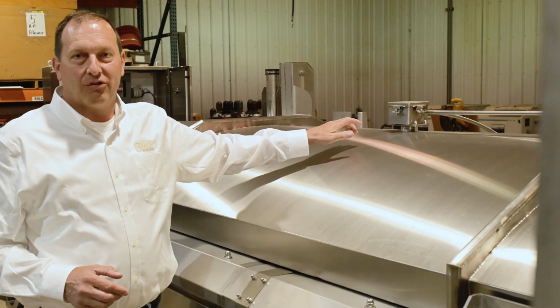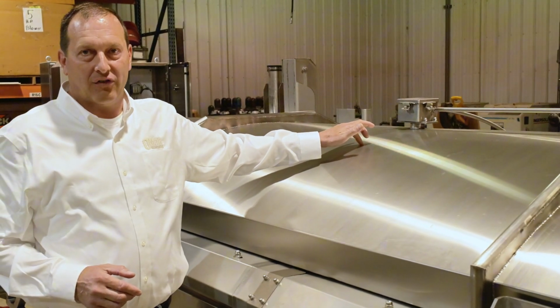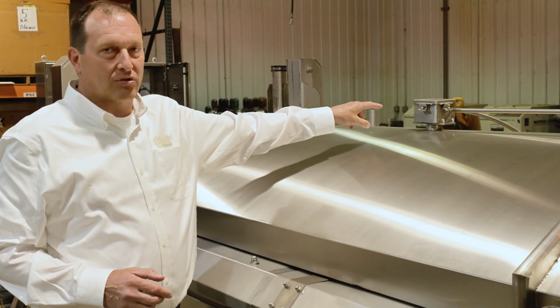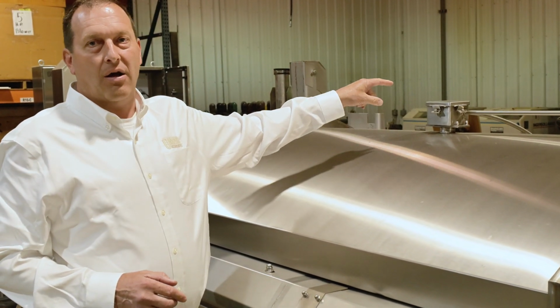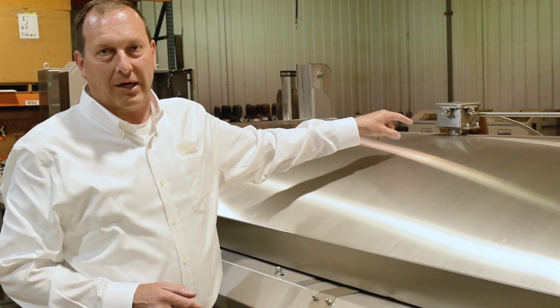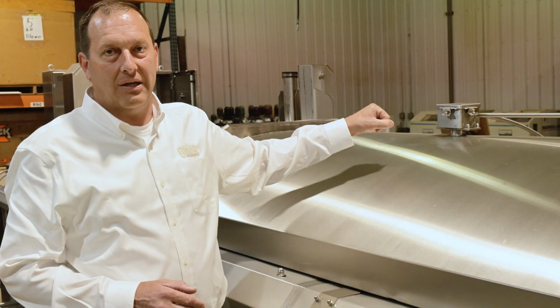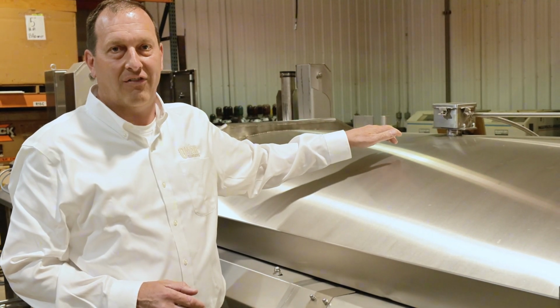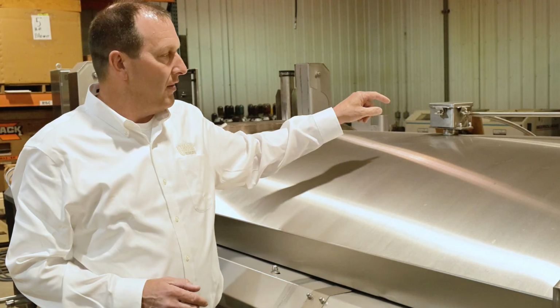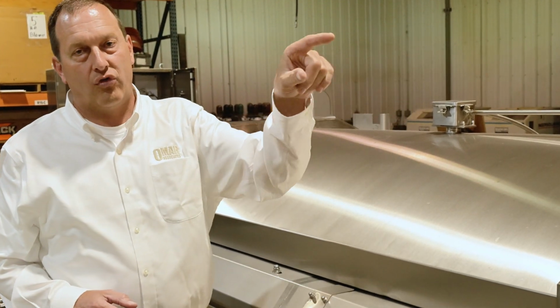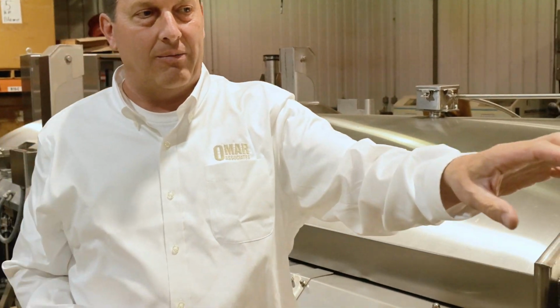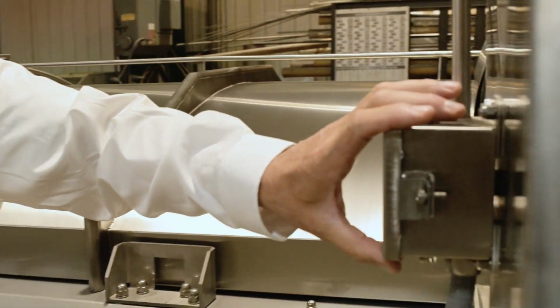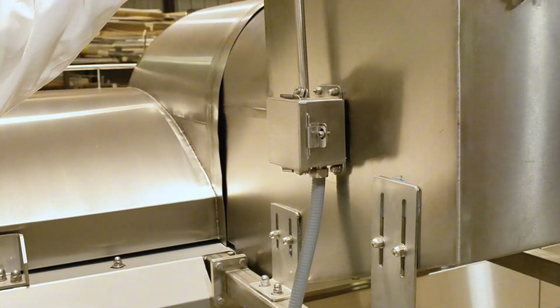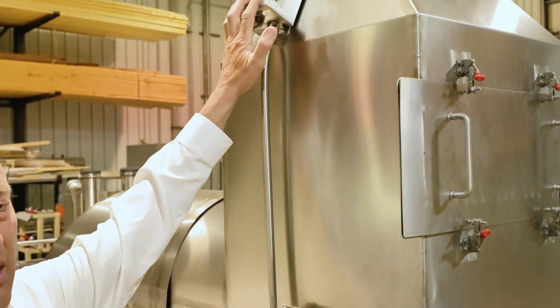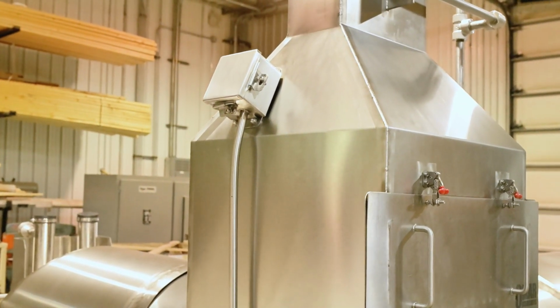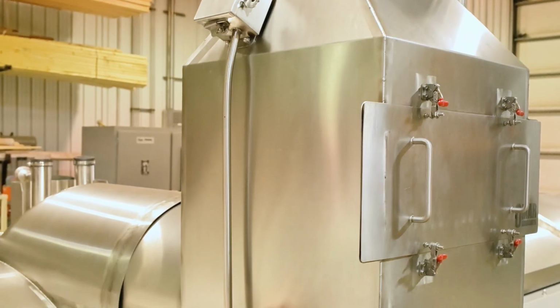The Omar fryer is pre-piped and pre-wired for fire suppression. So we have two temperature detectors in the hood of the fryer. Those detectors will pick up and close the circuit in the case of 100 degrees Fahrenheit above normal operating temperature. There are two in the hood, and there are two detectors also in the steam vent. So there is a detector here below the mist eliminator filter. There's a detector here above the mist eliminator filter. So any one of these four can release the fire suppression system.